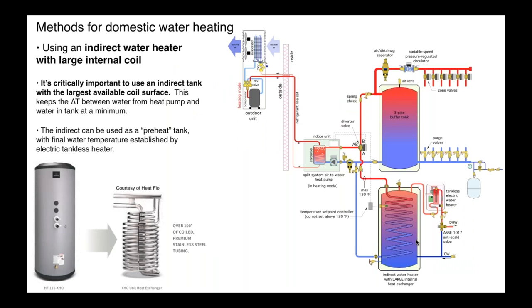Here's another option. That's an indirect tank. And the thing I really want to stress here is don't use an indirect that has a small coil in it. Many of the indirect tanks that are on the market in North America were built around the idea of a boiler supplying the heat. And if you look at the ratings, they're often rated at two heat source input temperatures to the coil. One is 180 Fahrenheit, the other is 200 degrees Fahrenheit. Well, you're not going to get anywhere near those temperatures with these heat pumps.